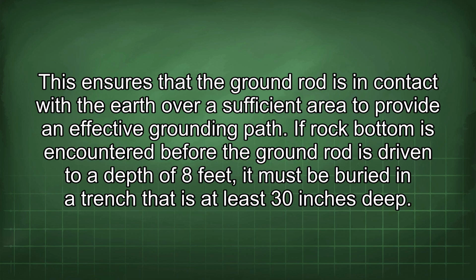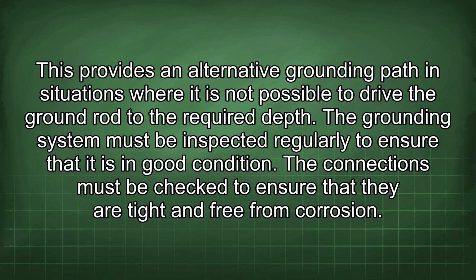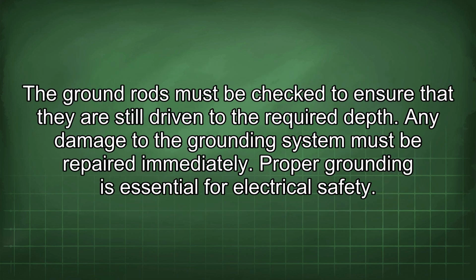If rock bottom is encountered before the ground rod is driven to a depth of 8 feet, it must be buried in a trench that is at least 30 inches deep. This provides an alternative grounding path in situations where it is not possible to drive the ground rod to the required depth. The grounding system must be inspected regularly to ensure that it is in good condition. The connections must be checked to ensure that they are tight and free from corrosion. The ground rods must be checked to ensure that they are still driven to the required depth. Any damage to the grounding system must be repaired immediately.